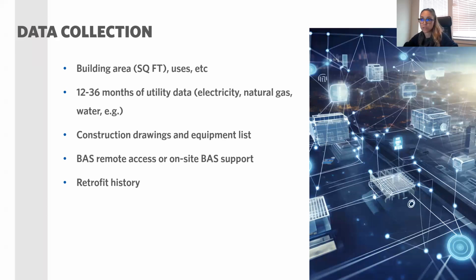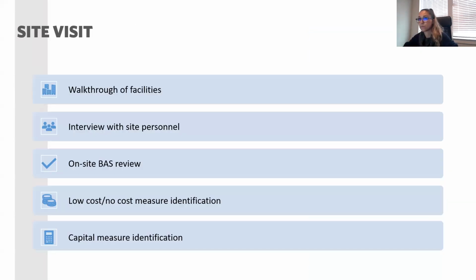The retrofit history is also very important for us to understand, especially if things have changed since the construction. Probably most important, the design information is most likely not applicable anymore for most of these projects due to the retrofits or the damages. I will show some examples in the upcoming slides. The next step is our detailed site visit. During the walkthrough, we try to collect as much information as possible by taking pictures, taking measurements of temperature, humidity, flow, or CO2 levels, based on the need, and interviewing the on-site personnel, which is really critical because they have the best knowledge about the building, its operations, and its problems.